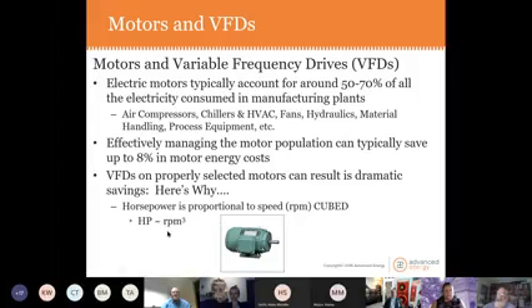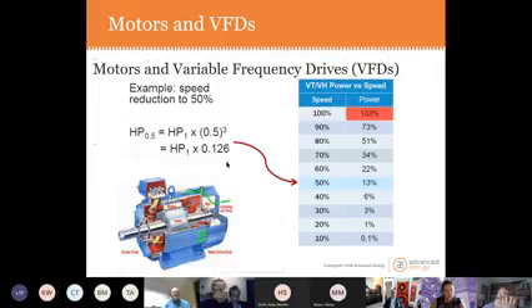and you can reduce the speed of the operation, say chilled water or a fan, you can slow those down parts of the day. The ratio of energy to the speed is to the cubed power. And an example of that is if you reduce the speed of a fan, for example, by half, that's 1/2, or half cubed is 1/8, and you actually only need 13% of the total power to run the motor at 50% speed. That's huge savings. If you have fans that are running at full speed all day long, but you don't need that much airflow all day long, there's a good possibility you could put a variable frequency drive on that fan and a thermostat feedback or some kind of air pressure or temperature feedback, and slow that fan down during parts of the day and save lots and lots of energy.